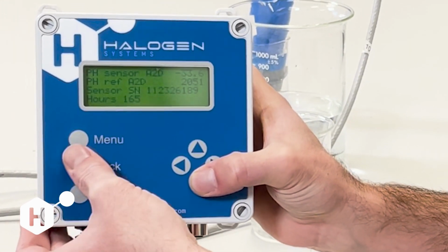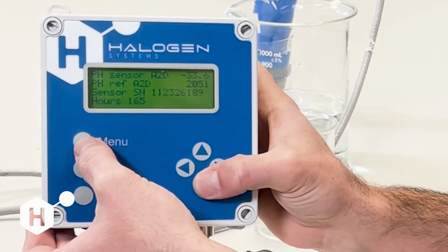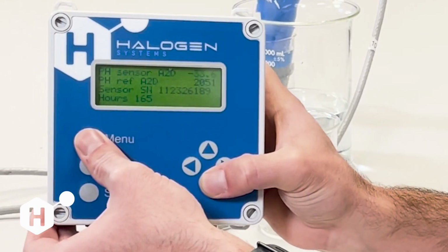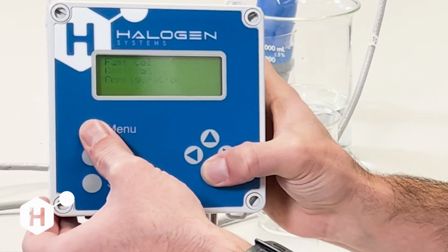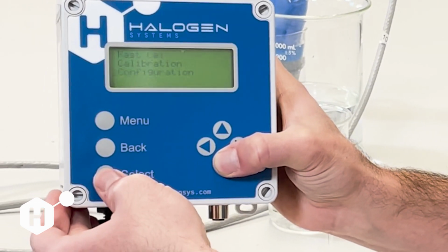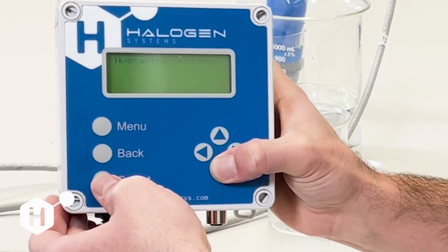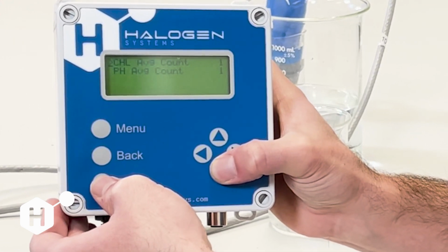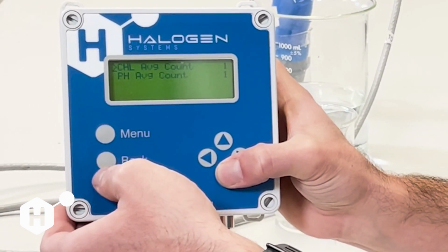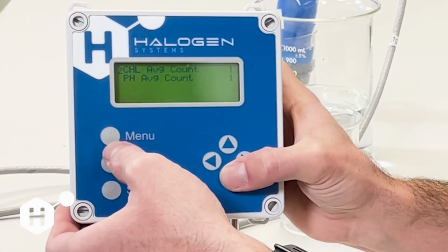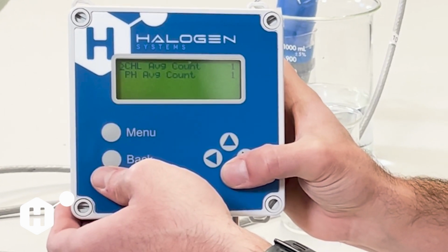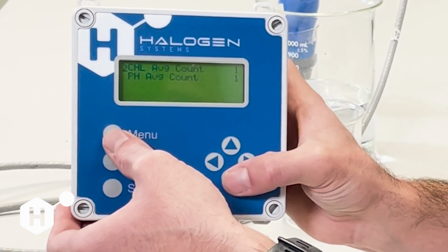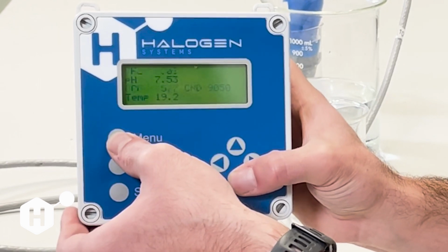This is also a good time to double check that we don't have any averaging turned on. So if we go to Menu, Configuration, and then all the way down to the bottom here we have averaging options. We're just going to want to double check and make sure that these values are both 1. Otherwise we're going to see that pH value dropping really slowly if we have like a 20 cycle averaging going.